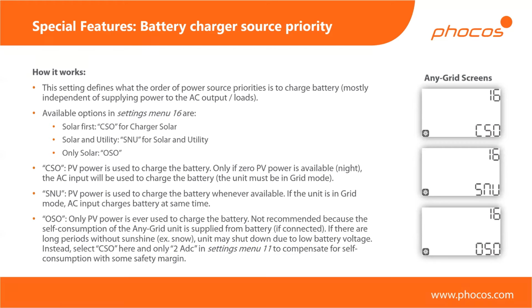And to avoid that from happening, we recommend that you do not use this setting in those scenarios where you could have snow on your PV modules, for example, but that instead you use the solar first setting. So you can be sure that during the day when the sun's shining, there's definitely nothing charging the battery from the grid, only from solar. And then when the sun is not shining, so again, for example, if there's snow on the roof or also during the night, then the grid will be used for charging.